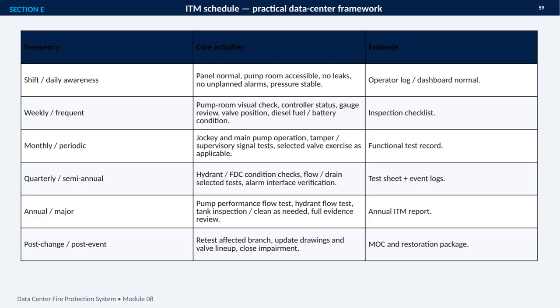This slide provides a practical ITM framework for maintaining a data center fire protection system over time. The key idea is that inspection, testing, and maintenance happen at different frequencies, and each activity should produce clear evidence. At the shift or daily level, the focus is awareness.